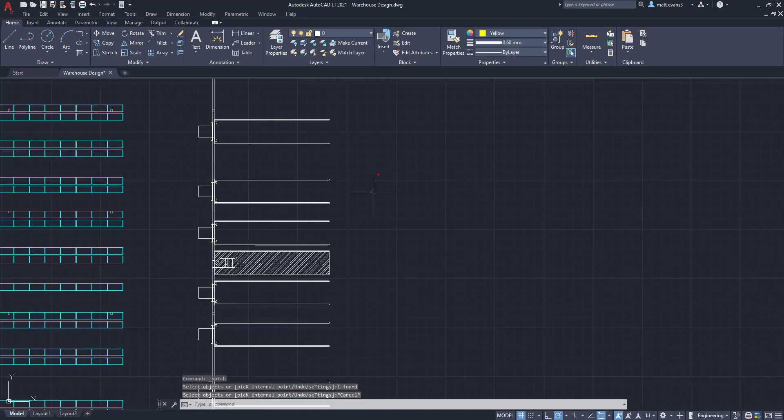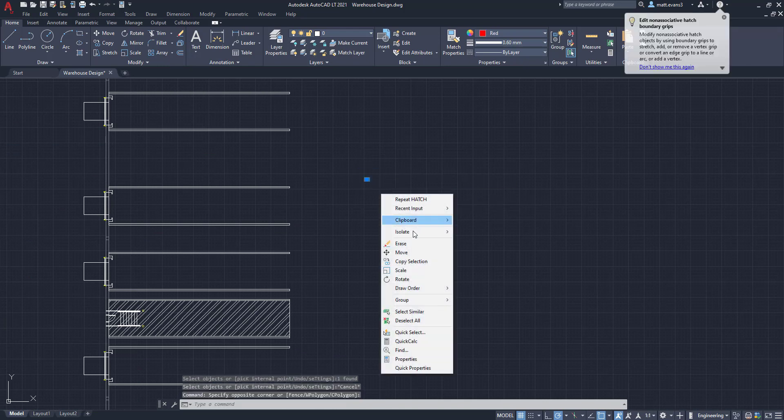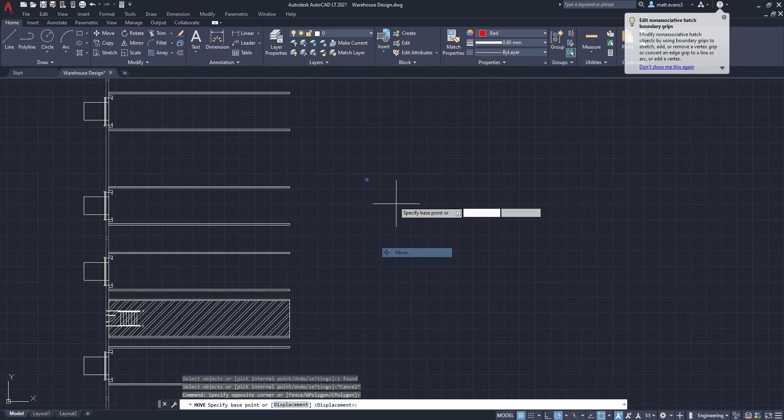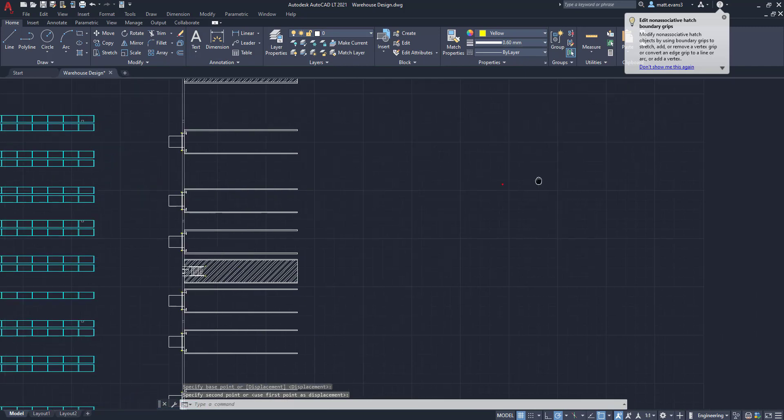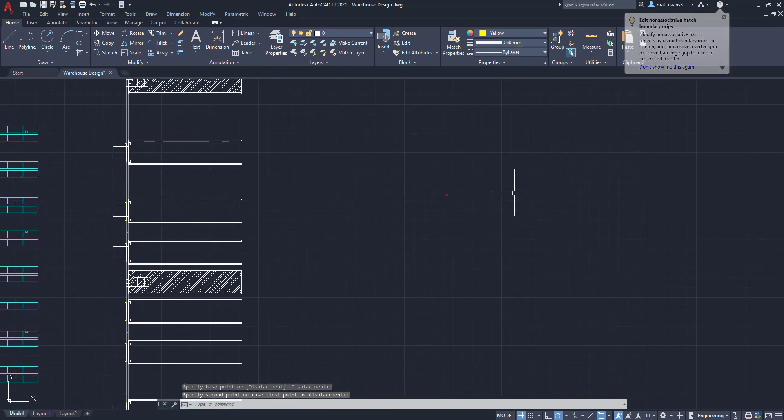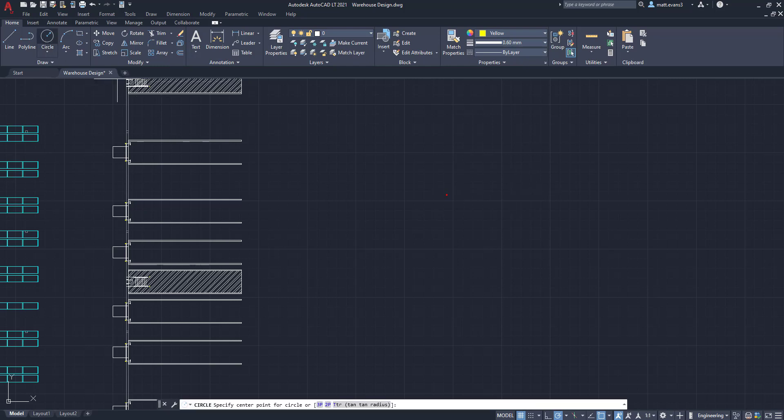Alright, so now we have our fire extinguisher. The next thing we're going to do is we're going to bring it out here and move it. And we're going to put a bigger circle around it. So in our municipality or the municipality that I typically work in, you need 75 feet between each fire extinguisher. Every 75 feet, you are going to need a fire extinguisher somewhere in the building. I need to be able to access one within that distance. So this is where AutoCAD actually becomes really useful if you're in the design stages or you're an engineer or a safety person and need to know where the fire extinguishers need to be placed.